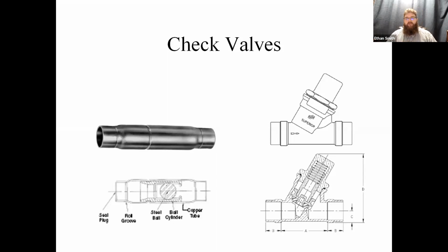Okay, let's talk a little bit about check valves. So check valves of this kind, the spring checks, are a little tougher to diagnose than the balls. But the first indication that you've got a check valve that's not working is, depending on which mode you're in, you should either have no temperature drop across the check valve, or you should have a very dramatic temperature drop across the check valve. So if this check valve were in the indoor coil, I would expect a significant temperature change in cooling mode across this valve, but no temperature change across this valve in heating mode. This thing should be wide open in heating mode. If I get a temperature drop through the check valve in heating mode, I know that I have a check valve that's not opening all the way.